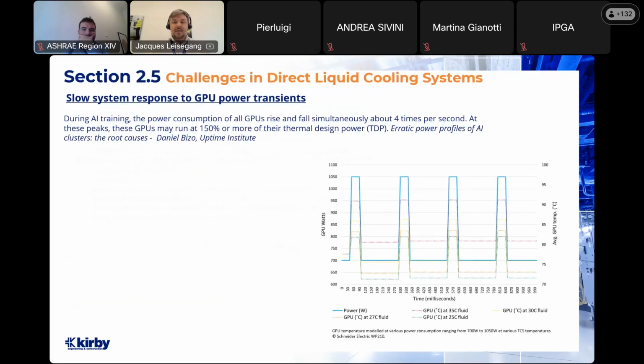And then finally, the other challenge that we need to deal with is the load profile of these GPUs. During AI training, the power consumption of GPUs rises and falls simultaneously about 4 times per second. At these peaks, these GPUs may run at 150% or more of their thermal design capacity.